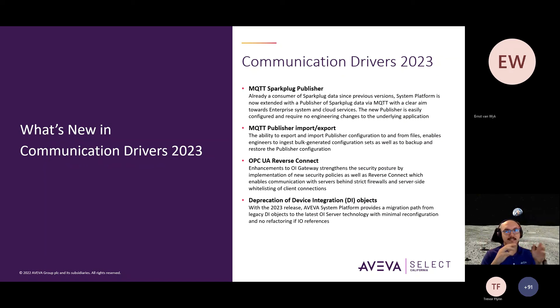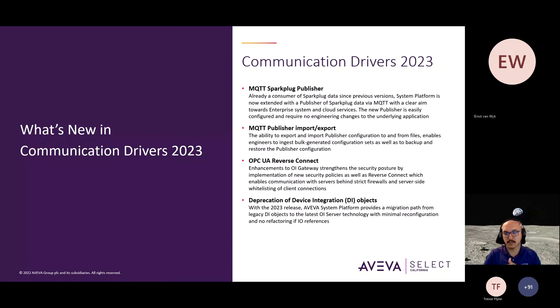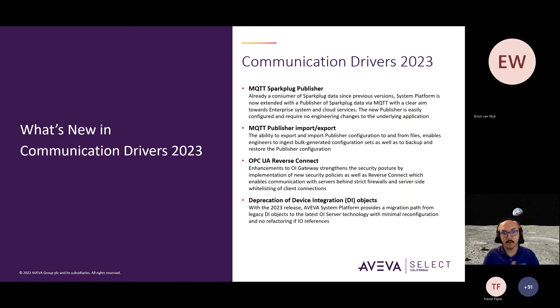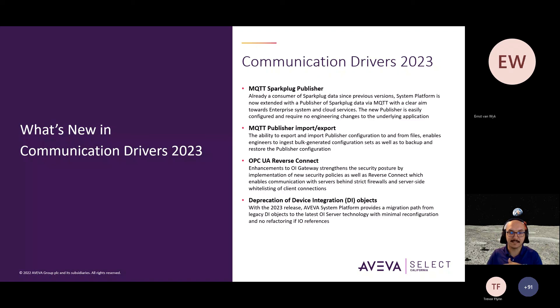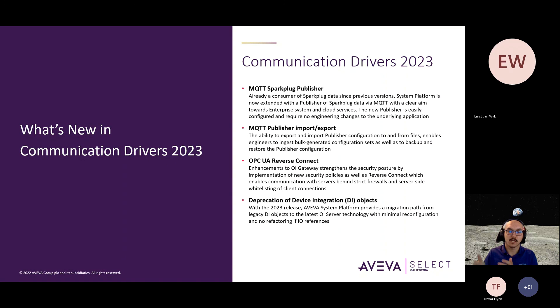In the past, you were able to take that whole infrastructure and create connections to the PLCs through the driver hierarchy in objects within System Platform. Those have been deprecated with modern releases, and there's now a conversion path with the device integration OPC client to get those legacy device integration objects back onto the latest OI server technology.